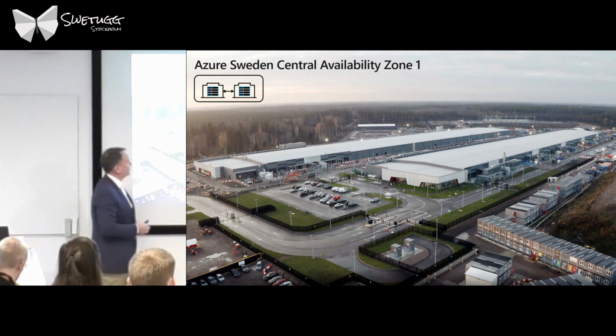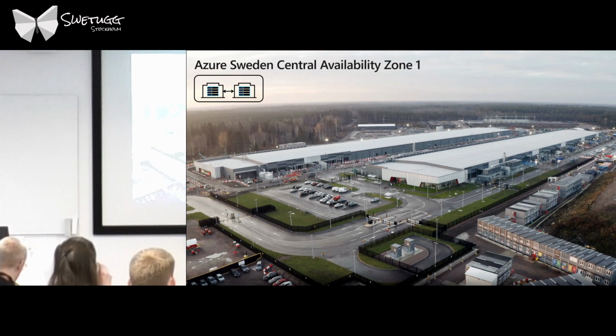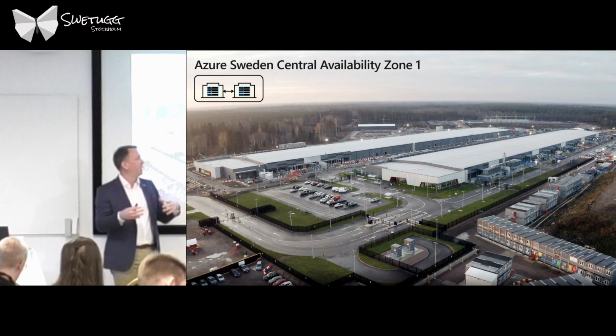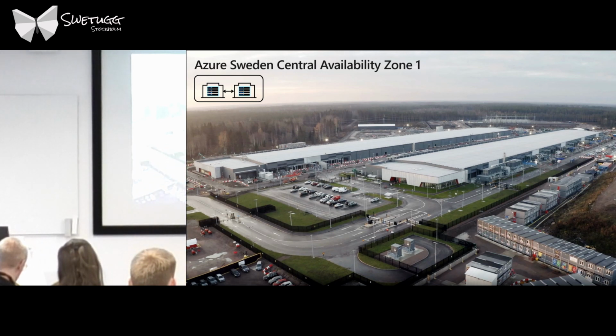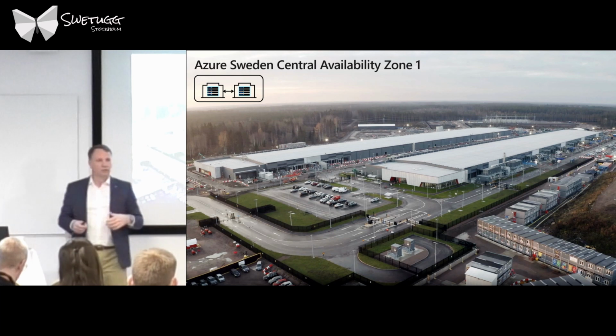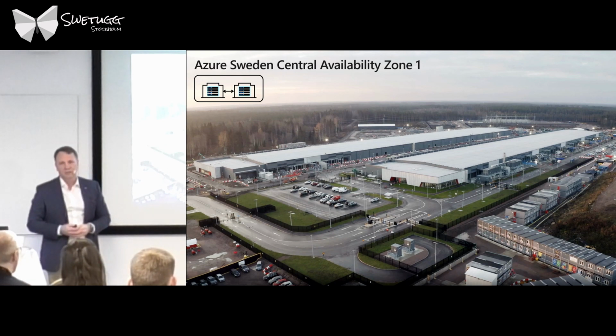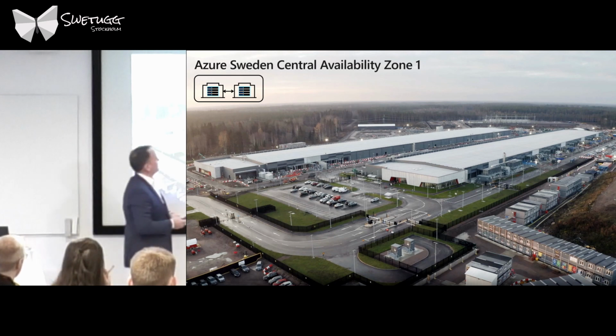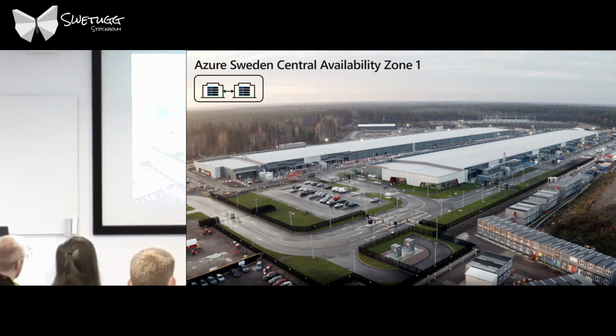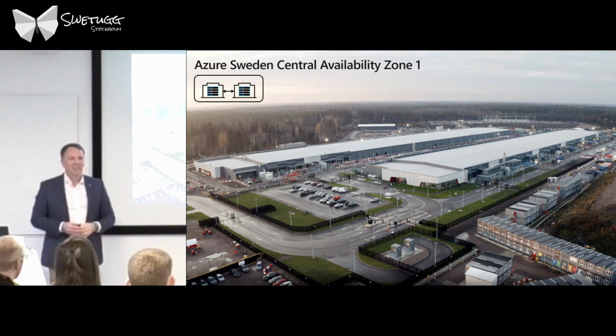we operate them in blocks. That means that each and every one of these sections is actually a colo block. And that colo block has separation of power, separation of network connectivity, etc. So each of these blocks has an individual power supply. So we can have failures on regions, we can have failures on a specific block, but not necessarily on the entire building, etc. Right? The other thing that I think is pretty awesome is that we're taking it straight from the high power grid. In Sweden it's called ställverk, which we have connected directly to the core power grid, providing the energy for this.